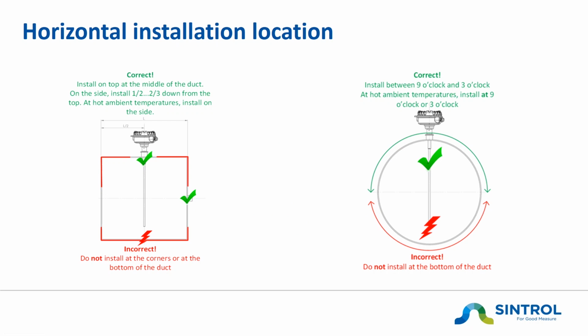Horizontal installation. We recommend to install the sensor always on top or on the sides of the duct. This is the same for square-angled or round ducts. Please don't install it to the bottom, because there we would collect all kind of dirts and maybe also condensation between the socket and the probe.